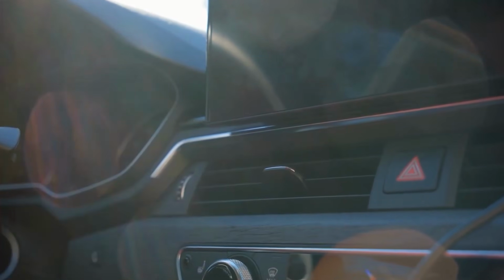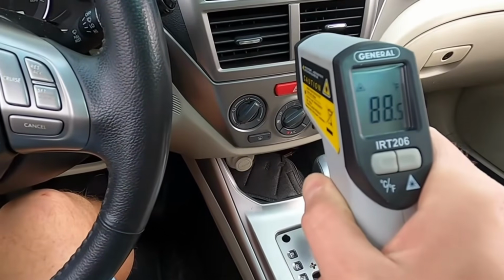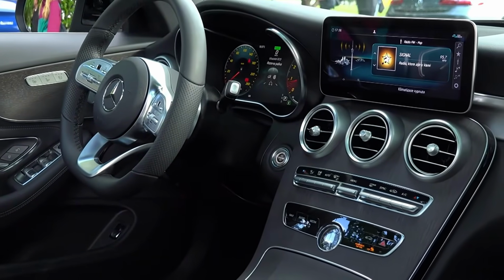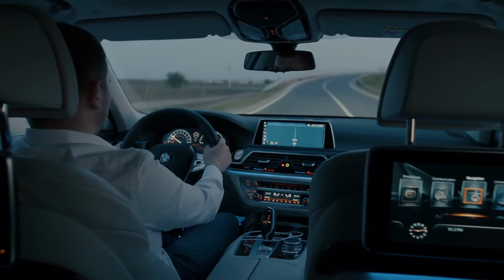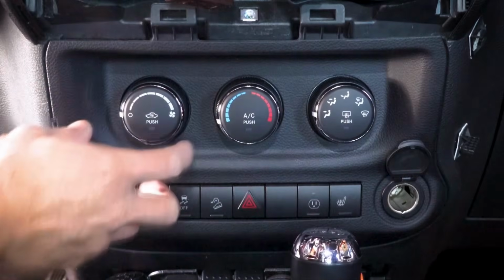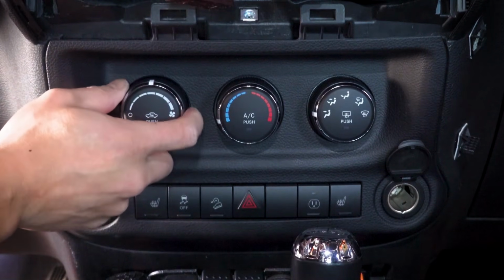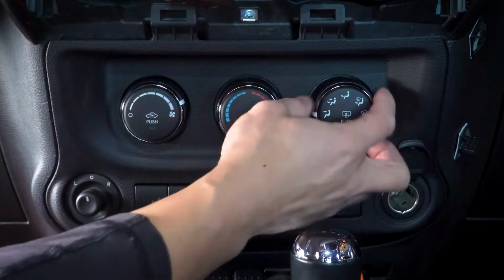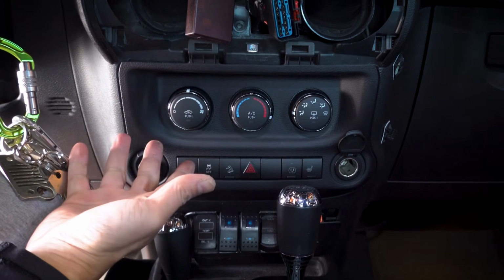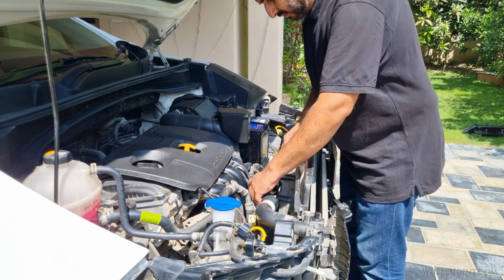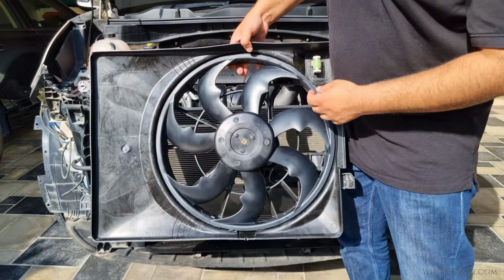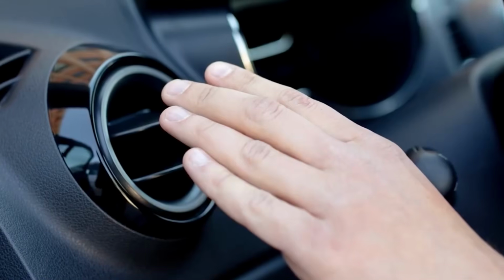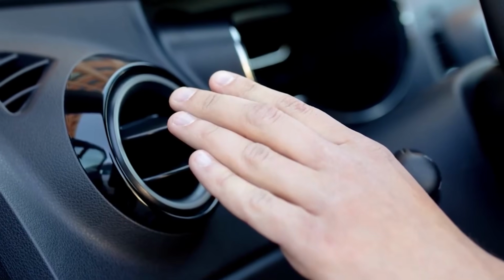Air conditioning isn't created by one part. It's the result of every component working together. Accurate diagnosis almost always costs less than replacing parts at random. Conclusion: cold air doesn't come from refrigerant alone. It depends on proper airflow through the condenser, the correct refrigerant charge, a healthy compressor, accurate pressure control, and a properly functioning HVAC system. When one part struggles, the entire system suffers.